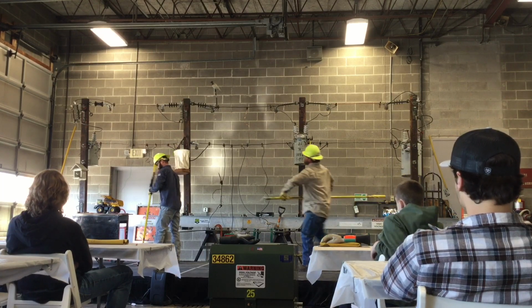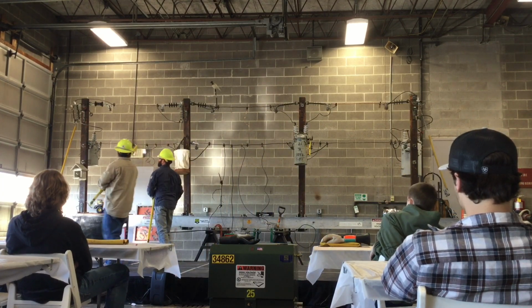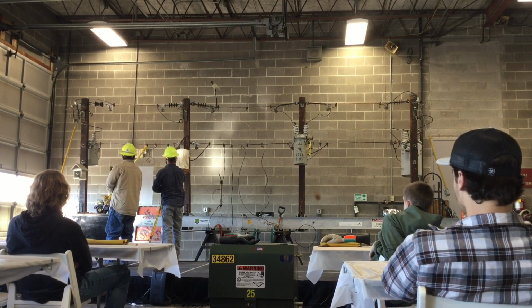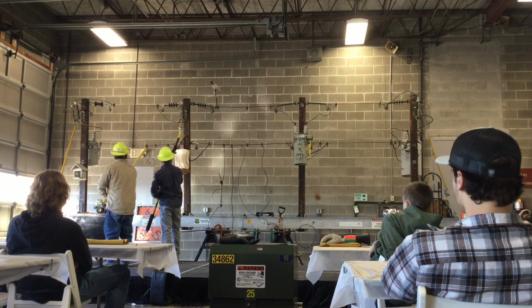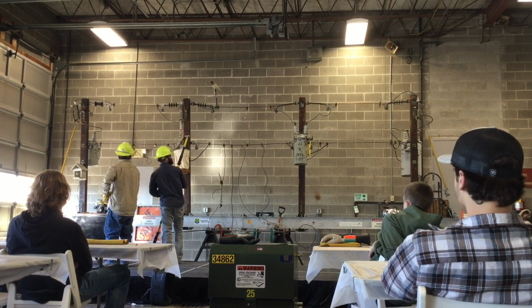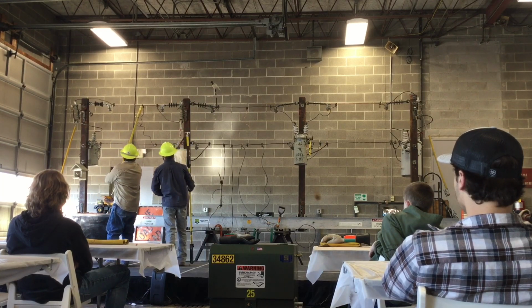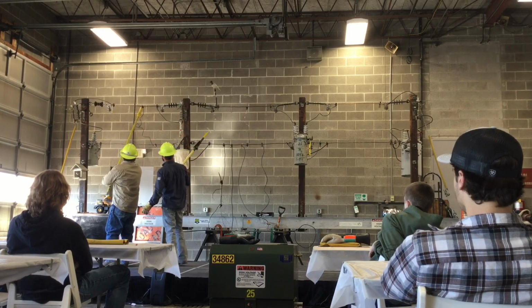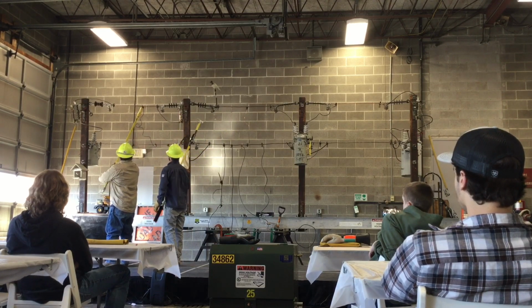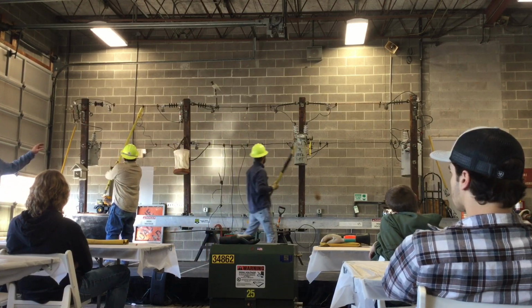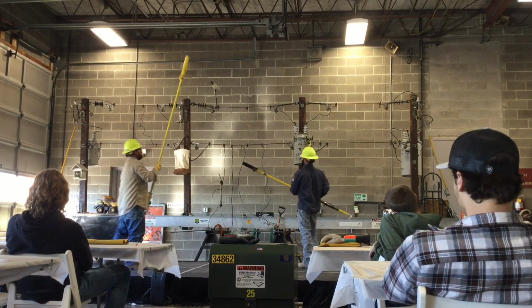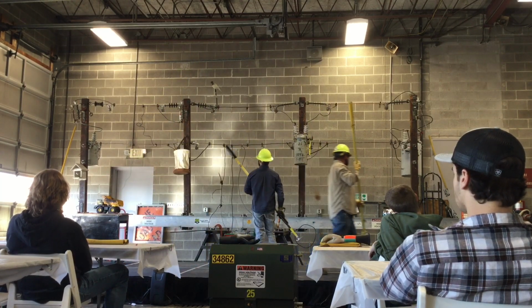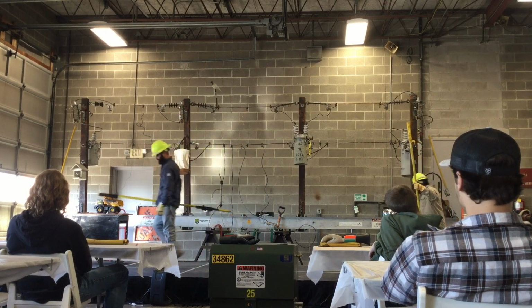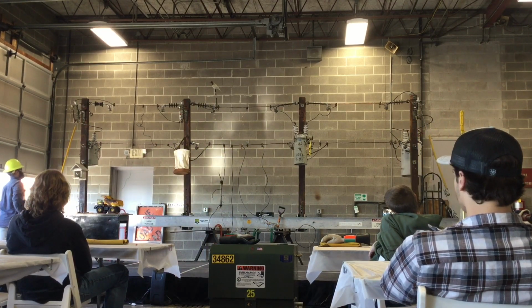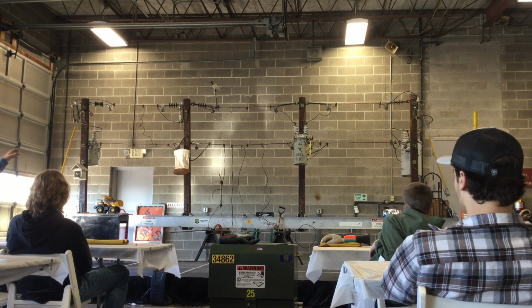The next thing we have, we've got a 200 amp cutout. The switch right here that Matt's getting ready to load this fuse door in, we took that solid copper door out and we're putting the fuse barrel in there. So let's say off Highway 15, you guys are familiar with that. We've got 3-phase, you'll have a single phase tap, maybe feeding 6-8 houses. We'll have one of these there, and basically this fuse is just sitting there, and it's basically one shot. So we put a ground on the downstream side of that fuse, and we'll show you. I want you guys to watch that red fuse door and count how many seconds it takes to fall out.